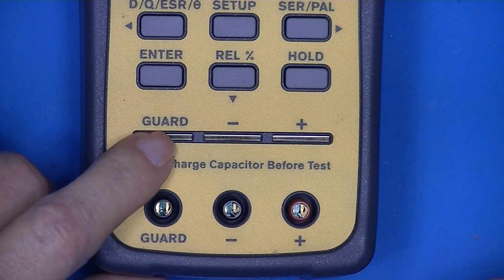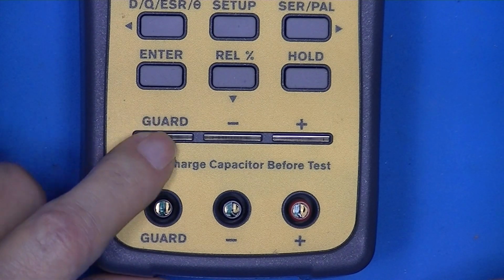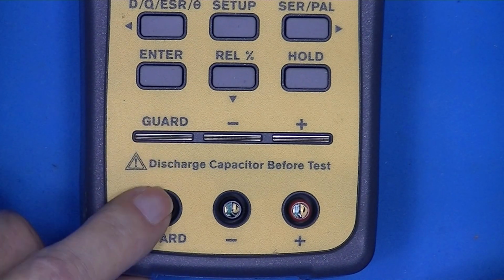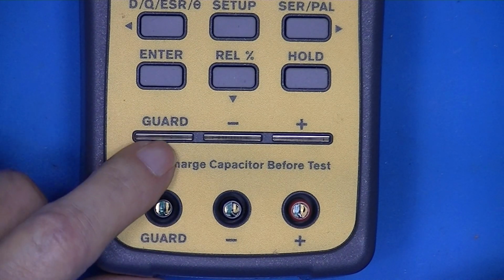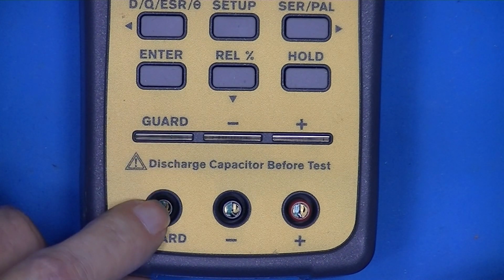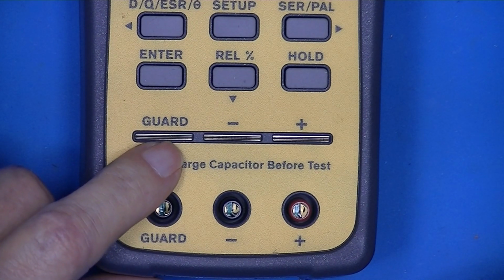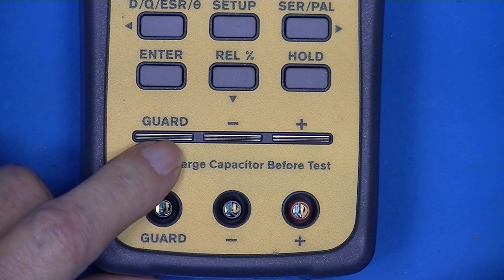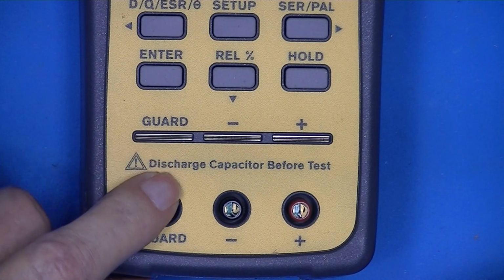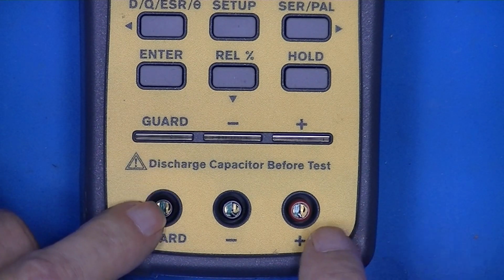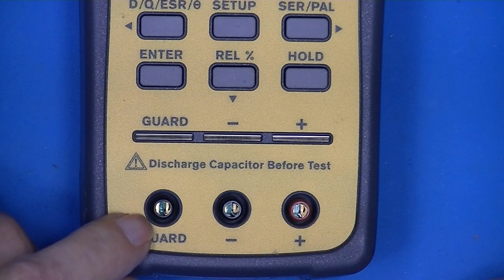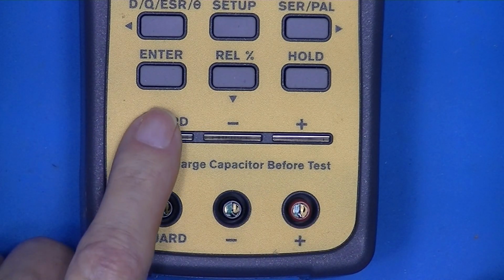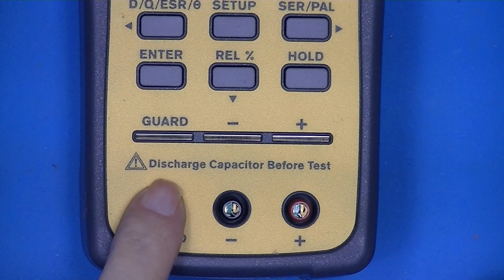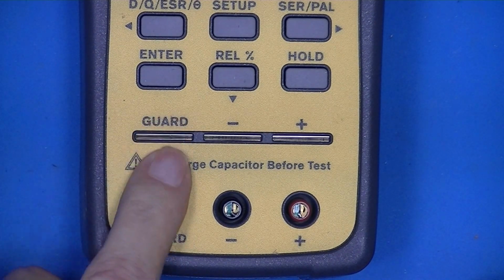Most of these simpler LCR meters, the guard connection is merely ground. On some of them, the guard is actually fed a tiny bit of the RF that's used to make the measurements. So in the LCR world measurement, it's called a guard, but most people call it a shield.